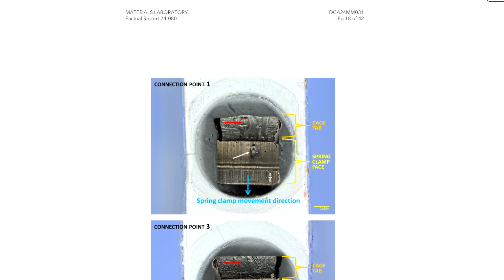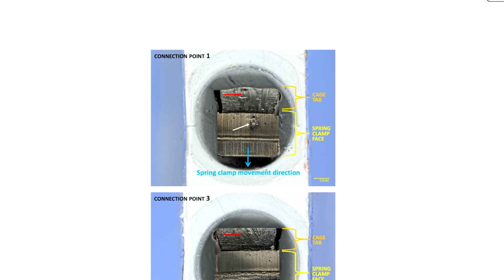Now they're looking straight down the hole into this. Remember, this is the bad one — this is where wire 1 was. You're looking straight down in there, and there's your spring clamp. Notice how you have that arc? There should not be an arcing mark on top of the spring clamp. Why? Because the wire is supposed to have gone all the way down the channel into the cage. It shouldn't be popping back up and arcing against the top of the spring clamp. That was the problem there.